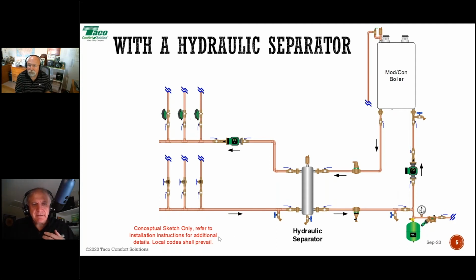All righty. Very good. We got some more questions here from George. Is it possible to see a hydraulic separator with two different pipe sizes, boiler side being one size and system side being the other? They don't have to be equally sized. I suppose they could, but the ones I'm used to seeing, George, are the same size, just for the reasons of not having multiple SKUs. If you want one, the biggest side is going to set the precedent of the pipe size.